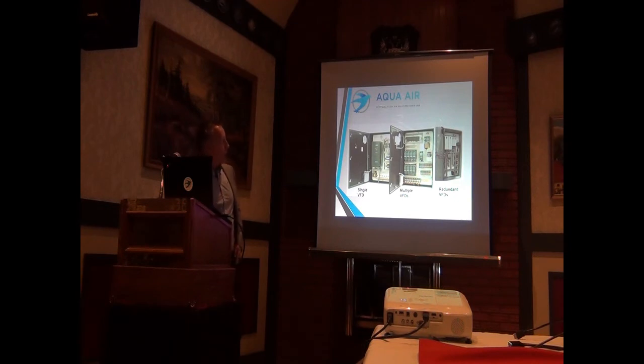If you need 100% capacity through the entire system, what you can do is N+1, N+2. If it's N+1, you want one extra motor and fan, and you build it into the fans and the motors. You'll have extra capacity by adding a couple extra fans or an extra fan and motor. When one fails, a light will come on in the system letting people know that one's failed, but the VFD or multiple VFDs will speed up the rest of the fans and you will get 100% capacity. The system runs just as it would if that fan hadn't failed. And again, then you can replace that at your convenience or schedule that replacement. Some people will buy an extra fan, housing, and motor to keep in stock just in case that happens. Another way to have redundancy.